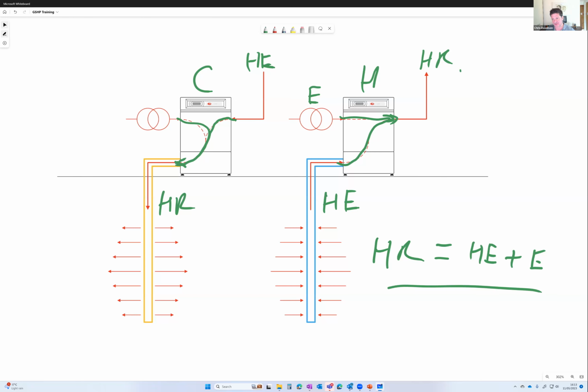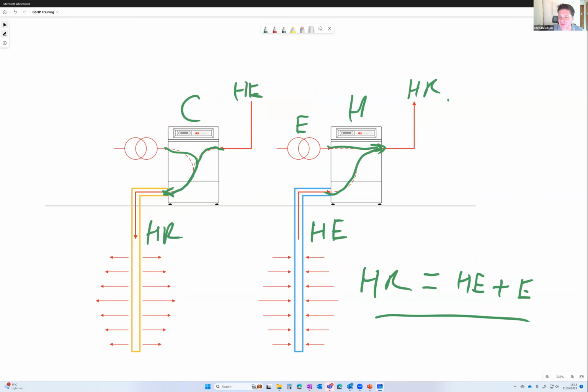So how do we design these things? The question we ask the design software is: given this heat being rejected into the building, and given the heat being extracted from the building, we need to understand that on the basis of peaks and also a monthly breakdown of those loads. Ideally we'd get hourly breakdowns of those loads, in which case we can be very accurate with our design.